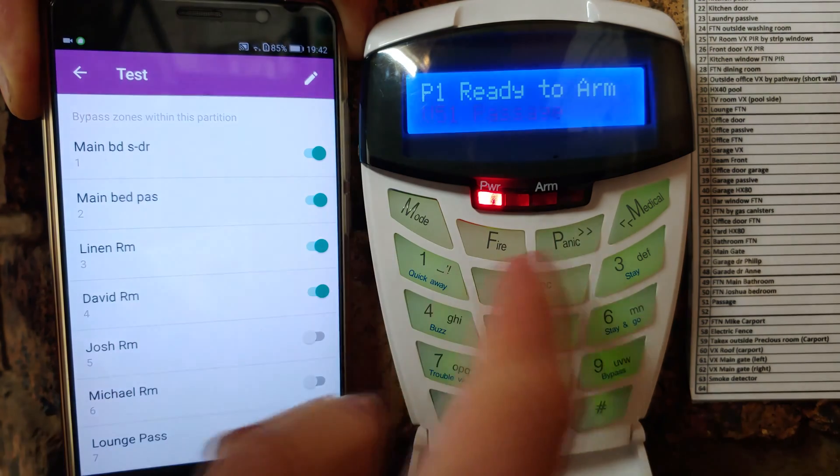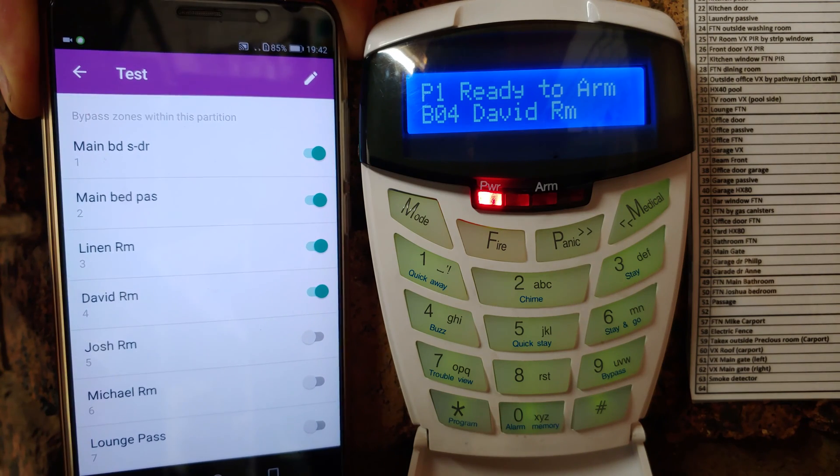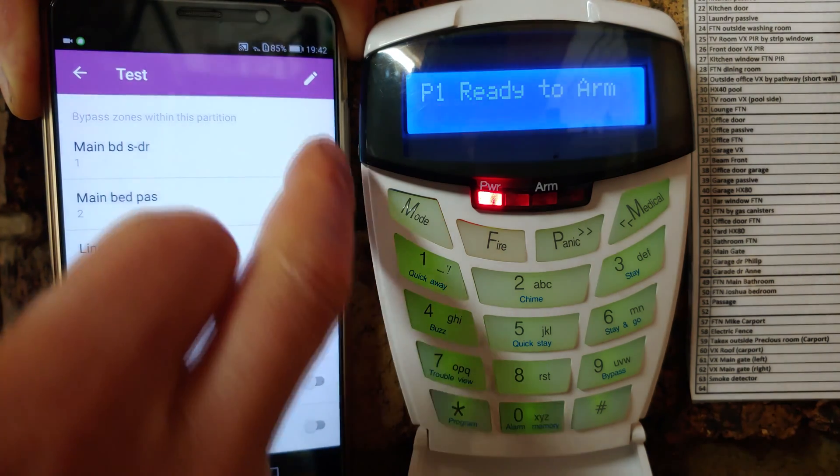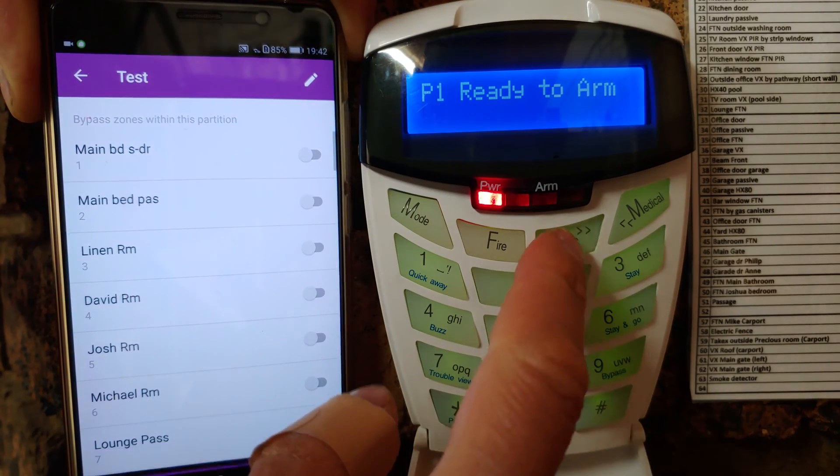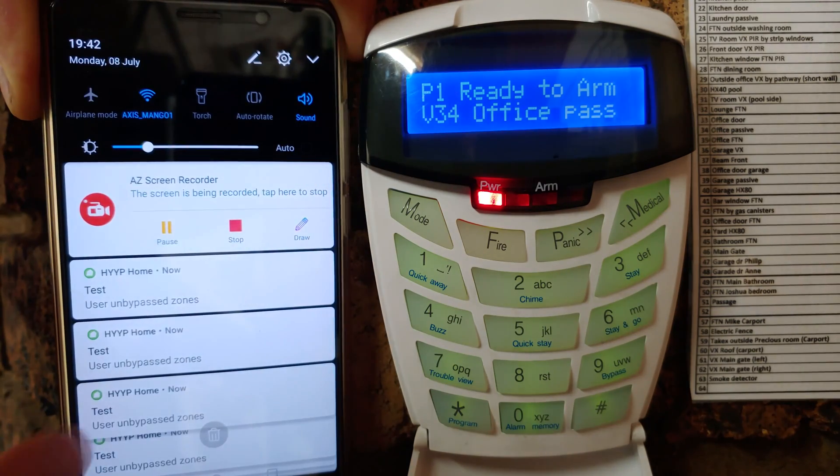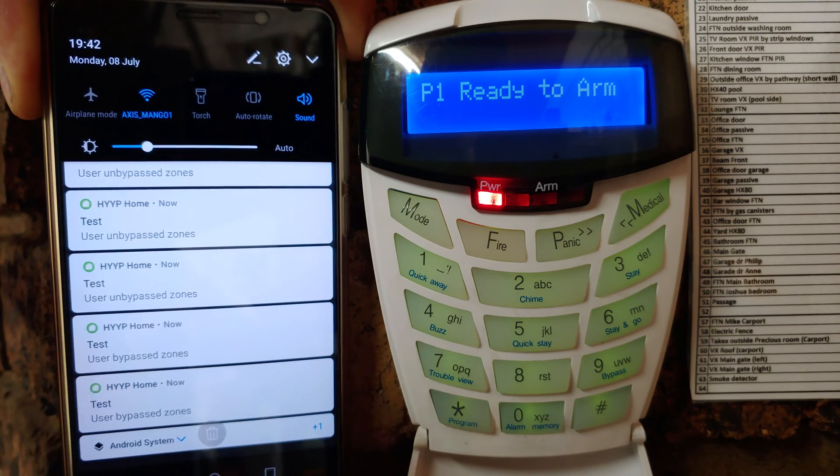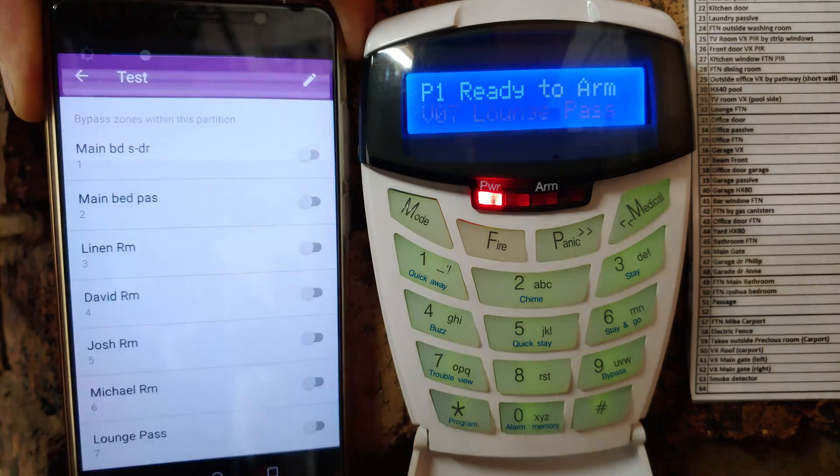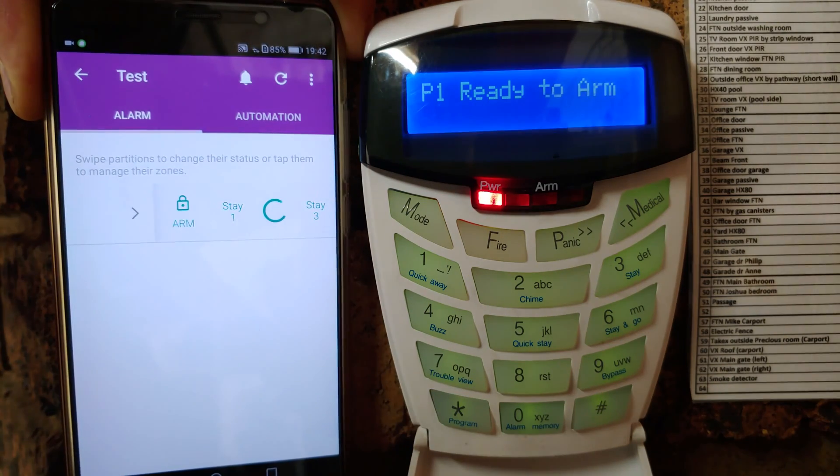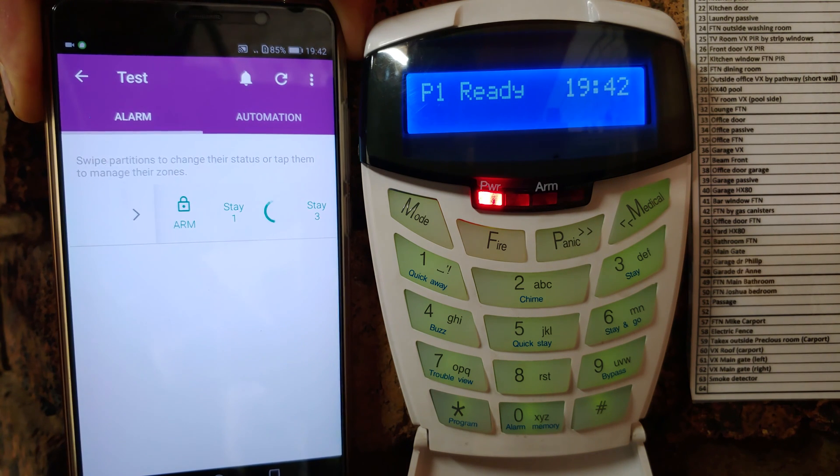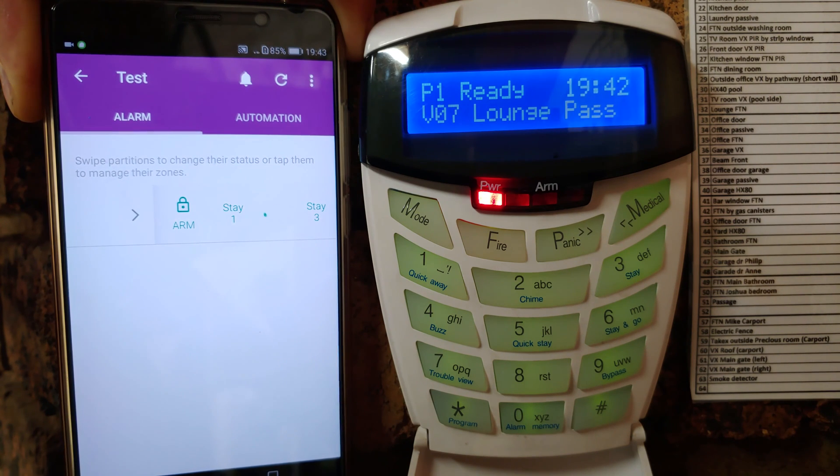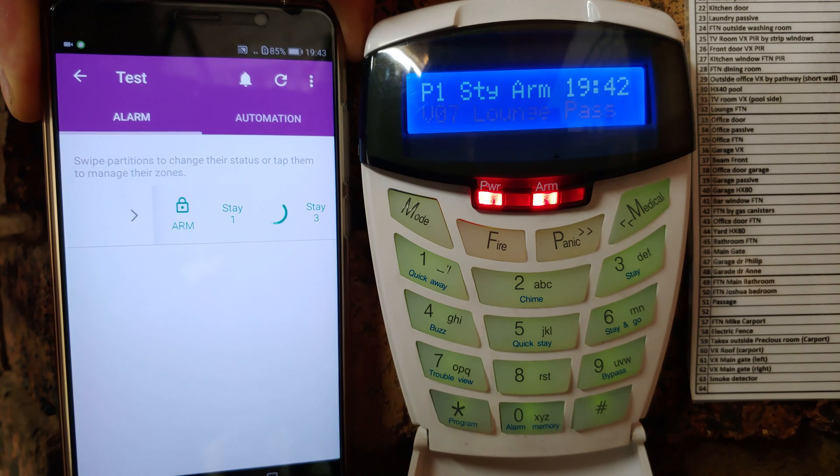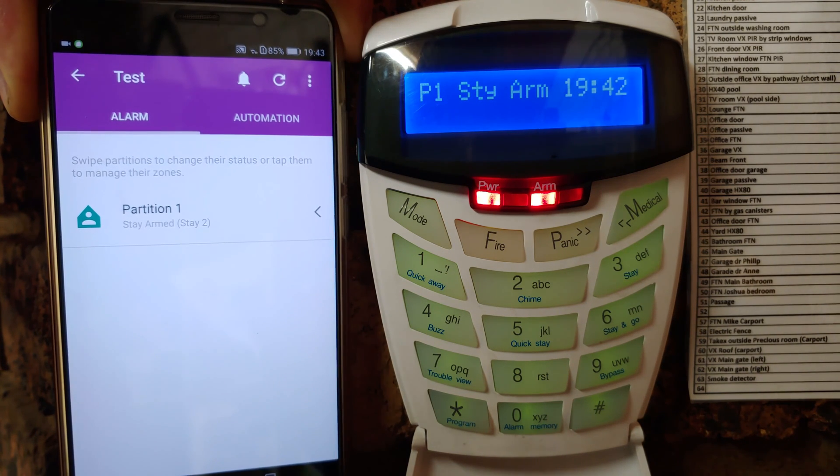You can actually see them being bypassed. There they are. I wouldn't call it real time, but it is close enough. I can put them back to normal. Zones no longer bypassed. You can see on the main panel, no longer bypassed. There are all these status updates coming to my phone telling me bypassed, not bypassed, and so forth. You can see how that is working. I'm just showing you the stay on. There you go. I'm going to stay on. There you can see, and then I get the notification saying it is now in the stay on position.